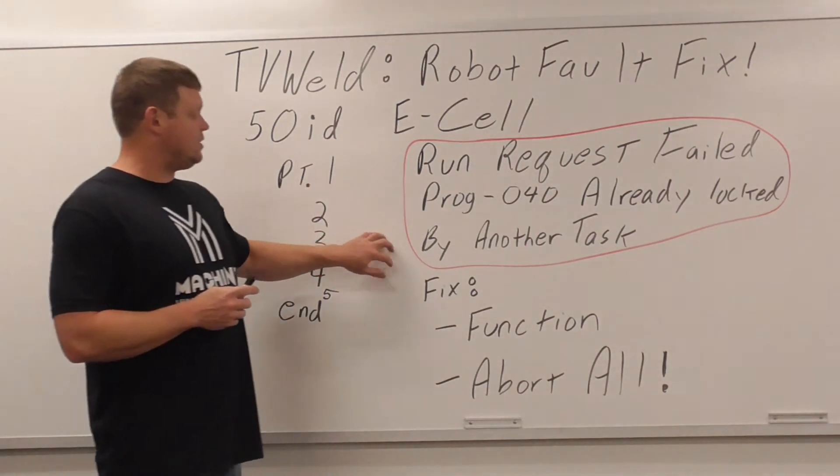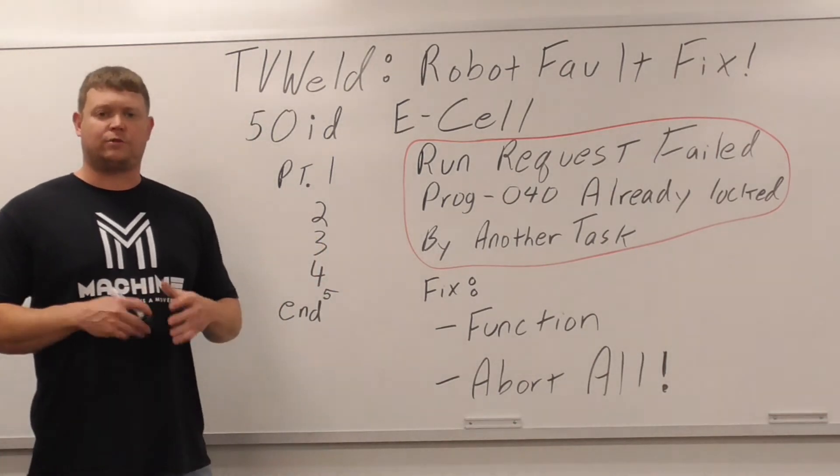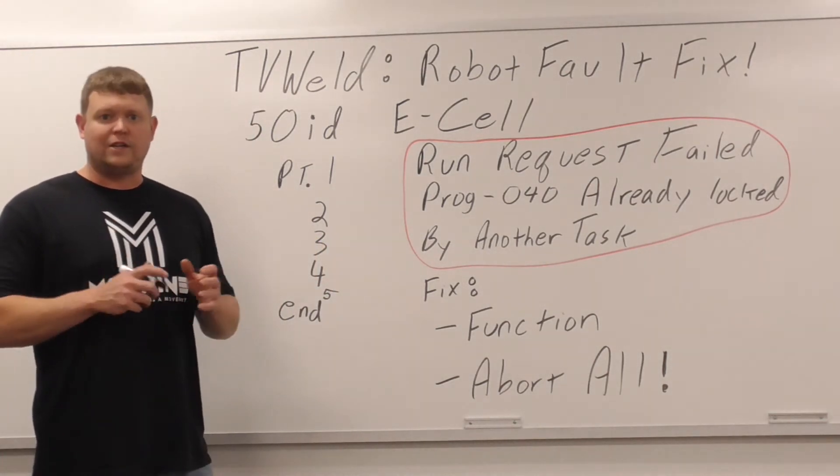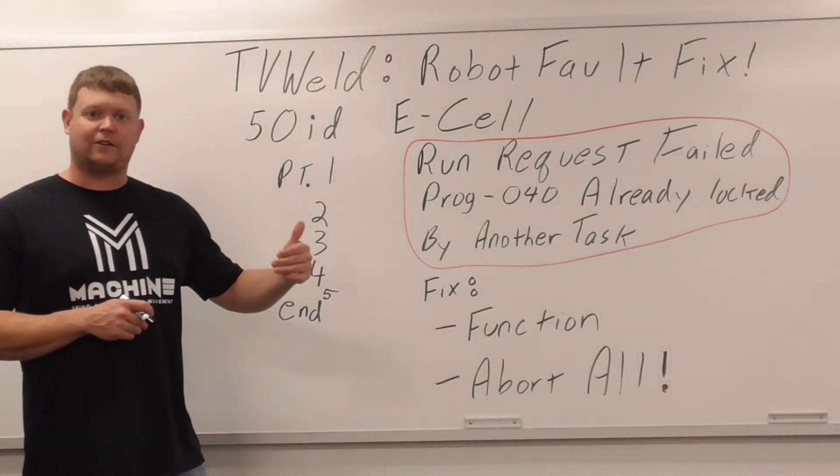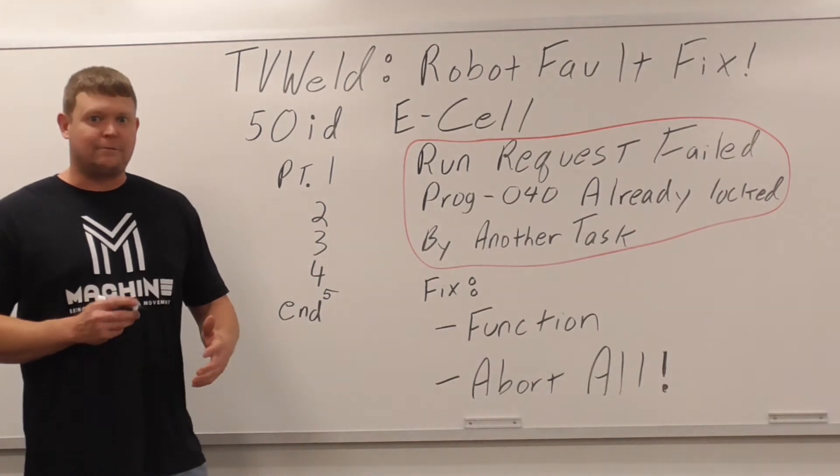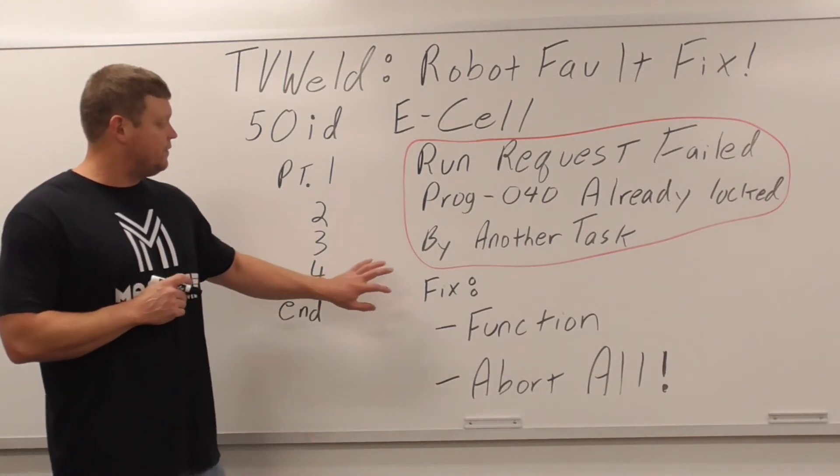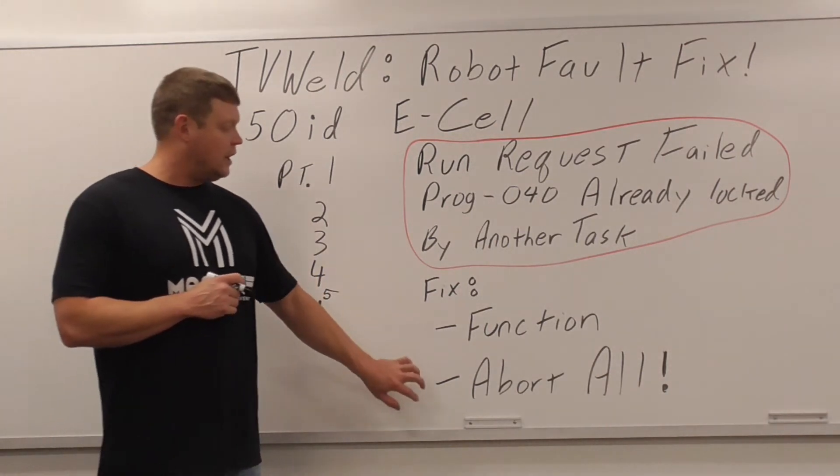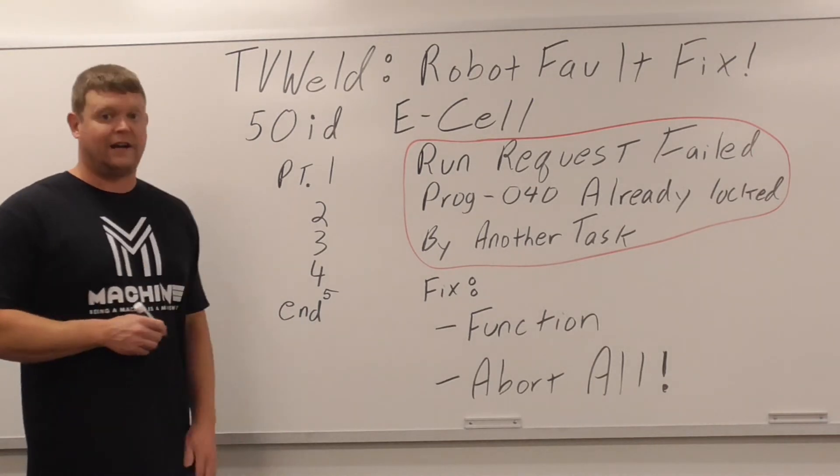When you get this, the way to fix it - I'm going to go out there and I'll screen up and I'll show you how to fix it on the actual teach pendant. I'll do it like twice because I tried doing this multiple times on the 50i and I kept getting the fault. To fix it, you go function and hit abort all, and then that'll clear it. Then you can go to point 1 and it works fine.